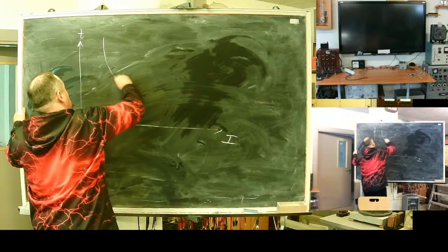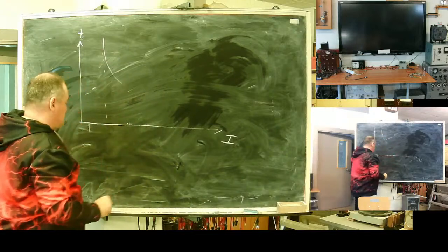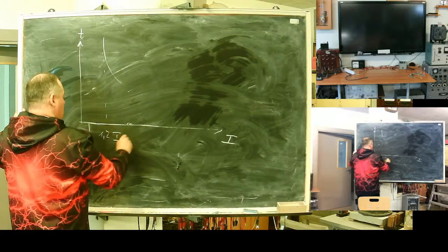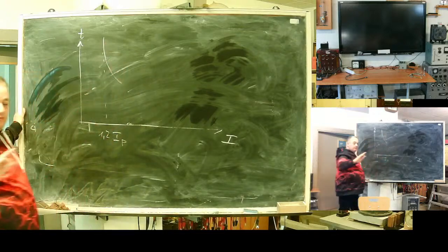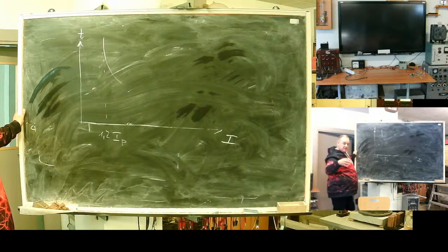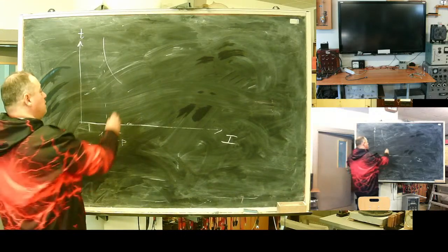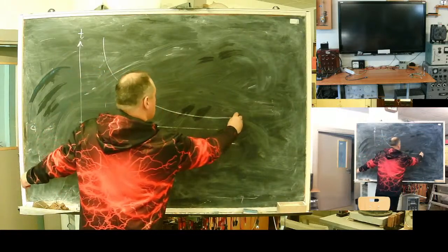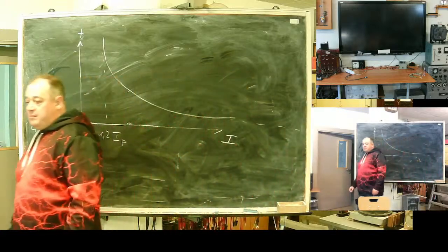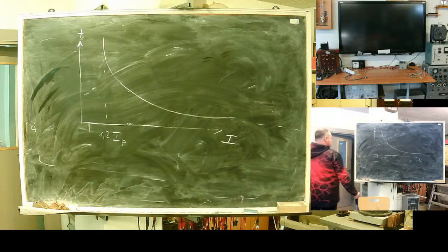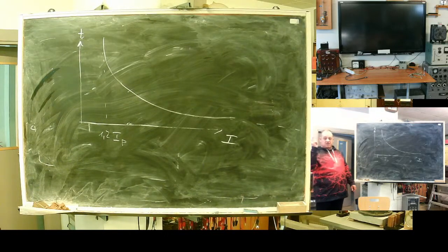At something like 1.2 of plug, the arm will swing. The toothed sector will come into junction with the rotating spindle, and you will get a characteristic like this, going to zero. Time-dependent characteristic. The higher the current, the faster the disk rotates, and in shorter time a trip signal will be sent.